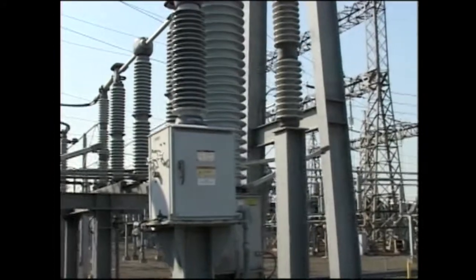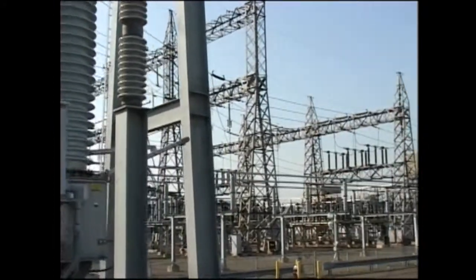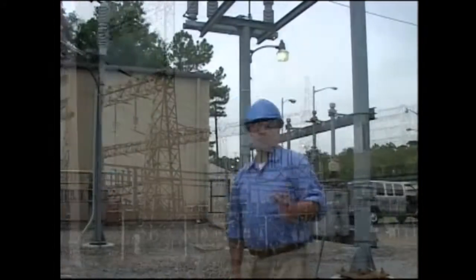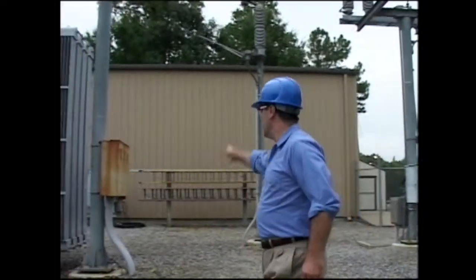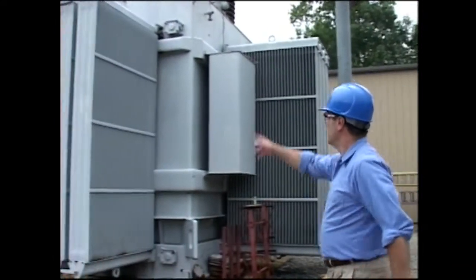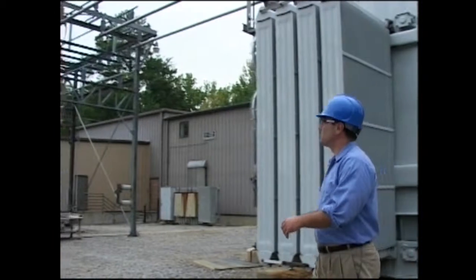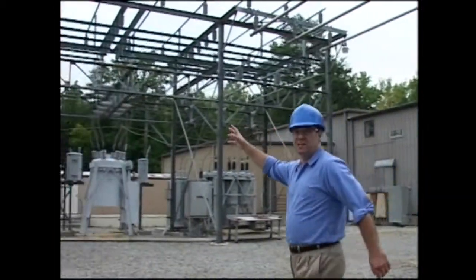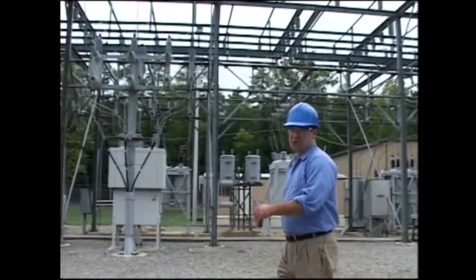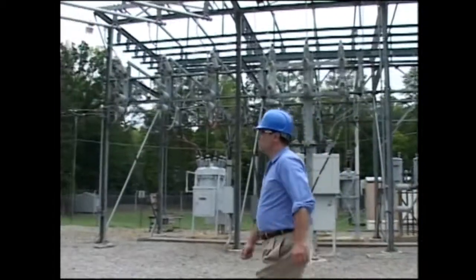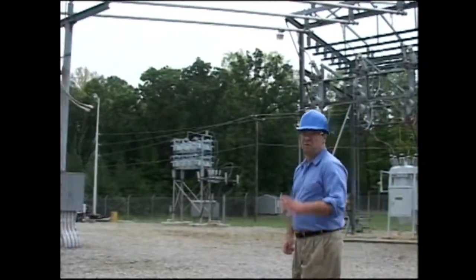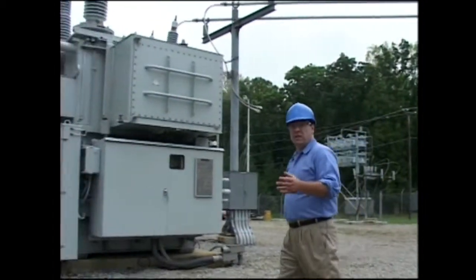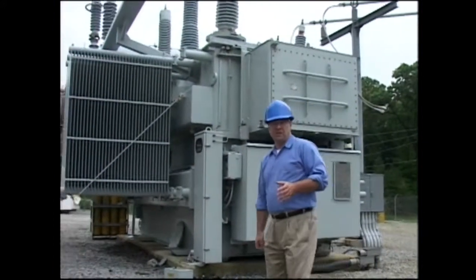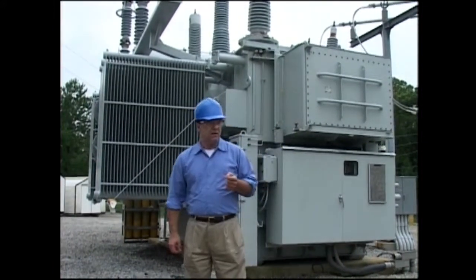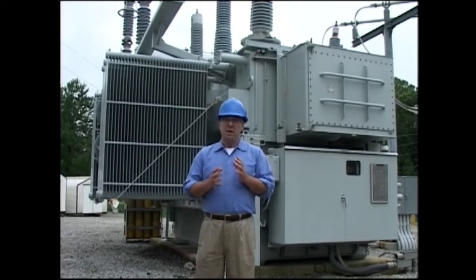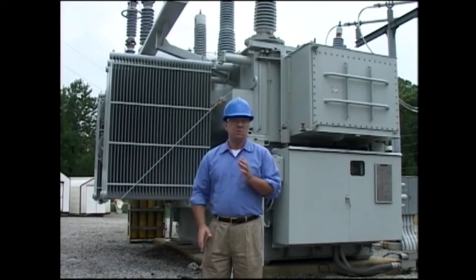An electric power substation has transmission and distribution lines coming in and out of it. Typically, some of the components include a control building, large transformers, structures to keep the lines elevated, and circuit breakers. Both transformers and circuit breakers are filled with oil, which insulates the internal electrical components. If a fire breaks out, the high voltage levels mandate special guidelines for responding safely.